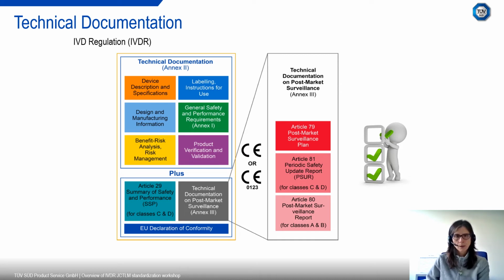In addition, as part of the technical documentation assessment, the notified body will review the summary of safety and performance. The detailed content of this is still being defined at the time I'm recording this presentation. However, this can be seen as an expanded instruction for use for highest risk classes. And as for the instruction for use, this will need to be reviewed by the manufacturer. And once EUDAMED is available, it will need to be uploaded into EUDAMED and will be visible to the public. Also part of the technical documentation assessment is the review of the manufacturer declaration of conformity.